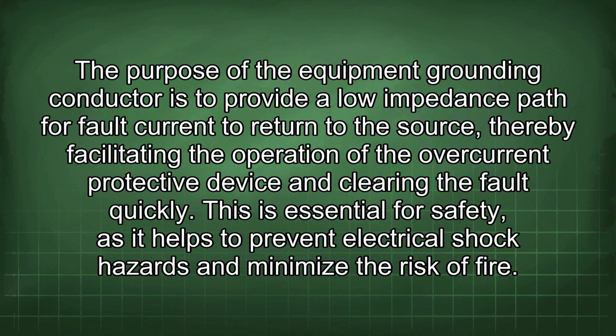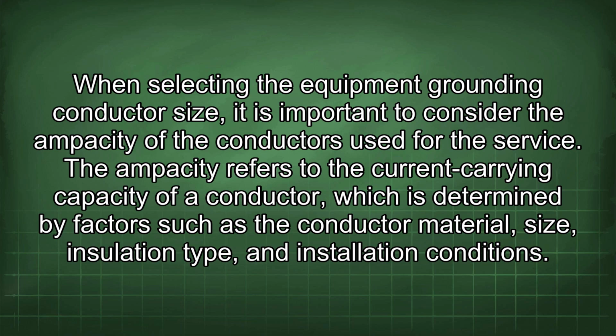The purpose of the equipment grounding conductor is to provide a low impedance path for fault current to return to the source, thereby facilitating the operation of the overcurrent protective device and clearing the fault quickly. This is essential for safety, as it helps to prevent electrical shock hazards and minimize the risk of fire. When selecting the equipment grounding conductor size, it is important to consider the ampacity of the conductors used for the service. The ampacity refers to the current carrying capacity of a conductor, which is determined by factors such as the conductor material, size, insulation type, and installation conditions.